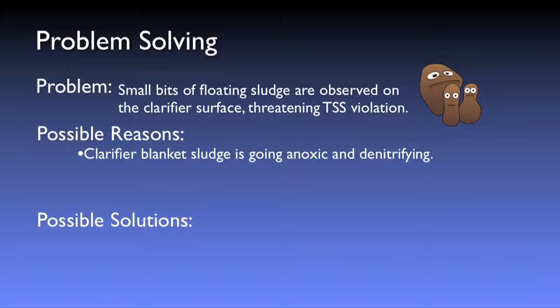Letting instinct take over, you spring to action by increasing the recycle rate, thus reducing the sludge inventory time in the clarifier, preventing this unwelcome denitrification.